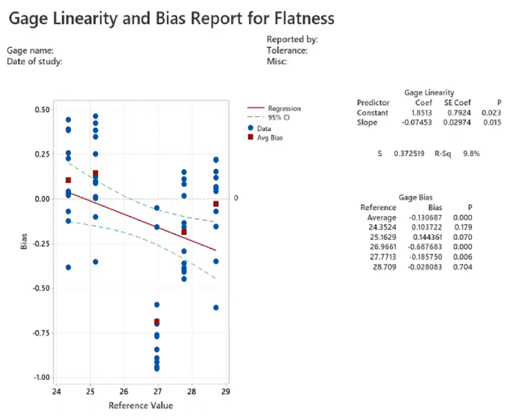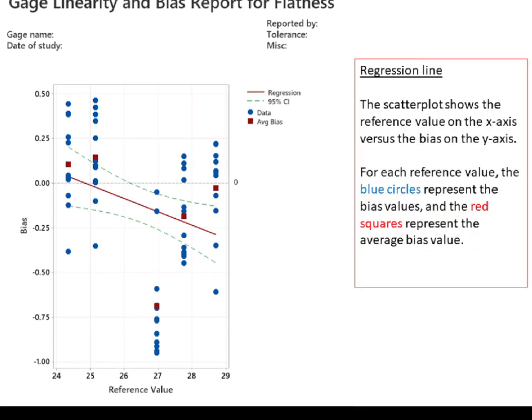Next, I will explain about the result of linearity and bias. Regression line: The scatter plot shows the reference value on the x-axis versus the bias on the y-axis. For each reference value, the blue circles represent the bias values, and the red squares represent the average bias value.